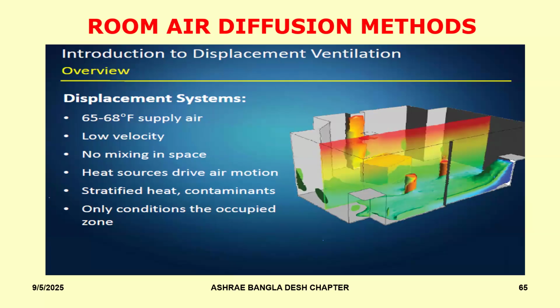So if the air is directly coming into the space, then the outlet velocity should be not more than about 70 feet per minute. Okay, so this is the kind of system that we are looking at. As the air leaves the outlet, it is still at a lower temperature as compared to the room temperature. Therefore, it is slightly heavier than the room air, and therefore it settles down to the floor.